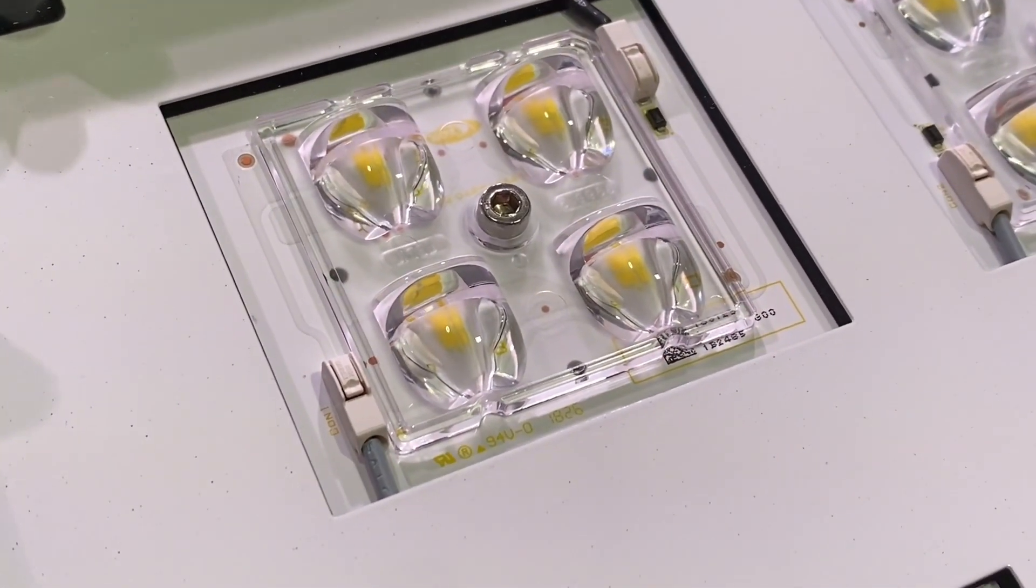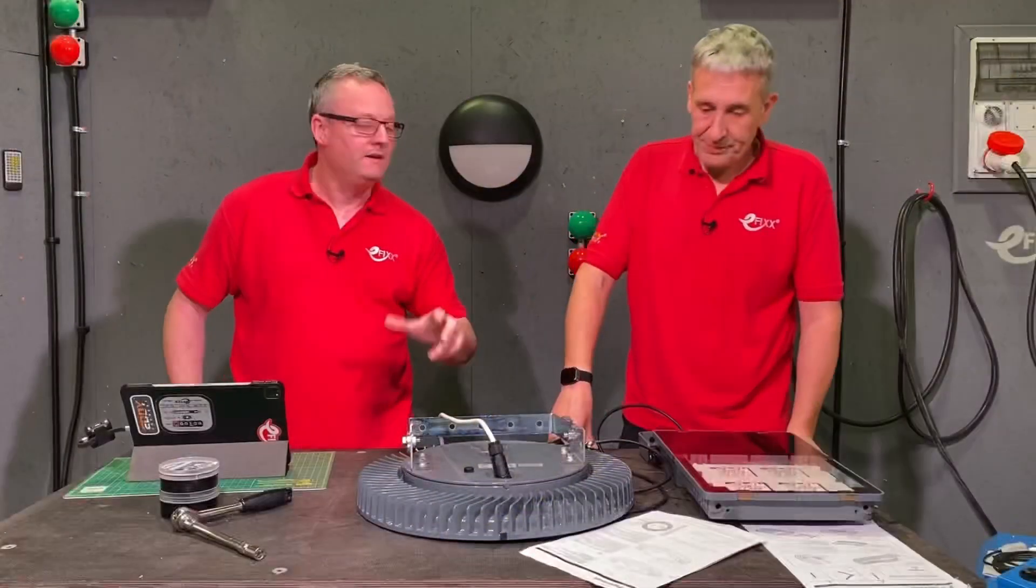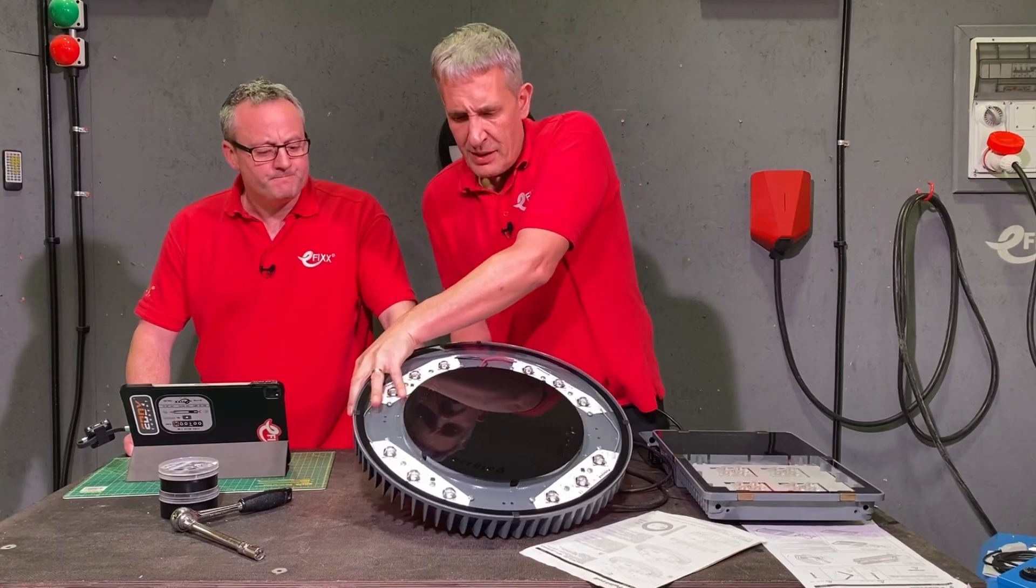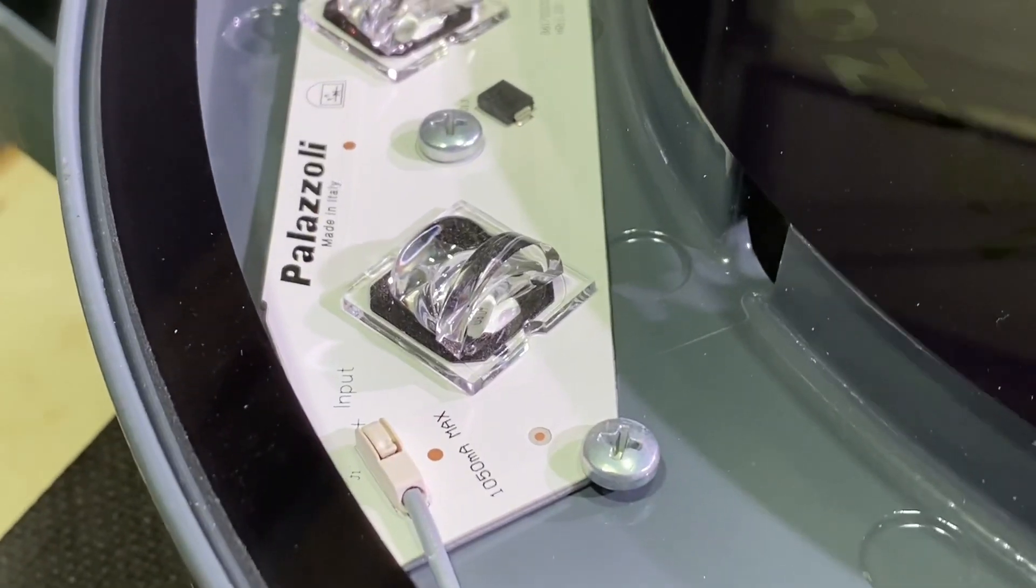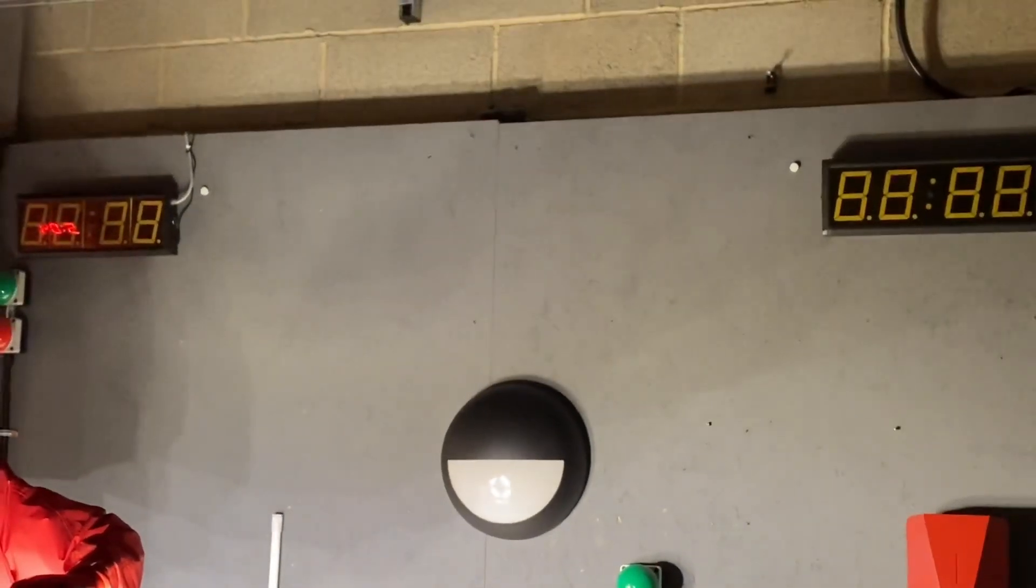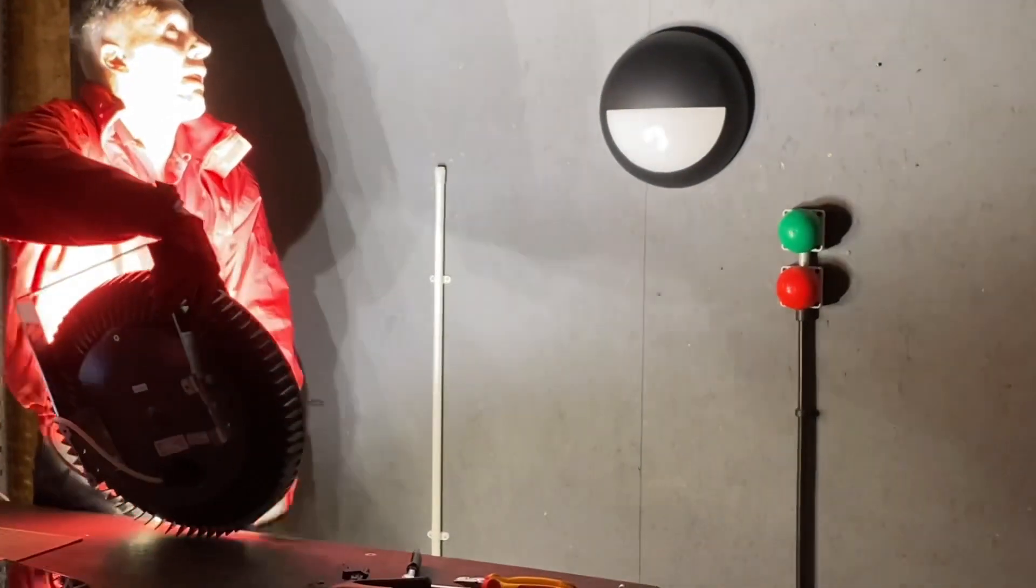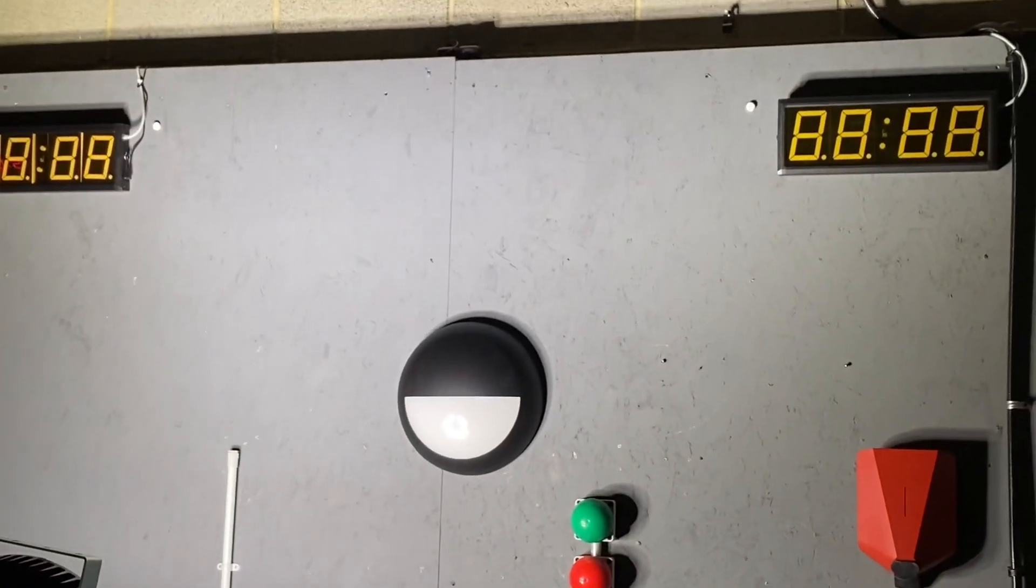Okay, when it comes down to quality, I think then optics, because that's really where we're going to see the benefit of a quality light fitting. Talk me through the optics, Gordon. So if I just flip this version over, there are some very different optics to what you used to see on a lot of high bays that you see possibly off the shelf. And obviously, by tailoring the light, you can use less fittings and use them in different applications. So this is a high bay light, but it's configured to be mounted on the wall. So when we do that, that means we want to push the light forward, from the wall, not back behind the wall, and we want to spread it out at an even angle to achieve the maximum spacing between fittings.